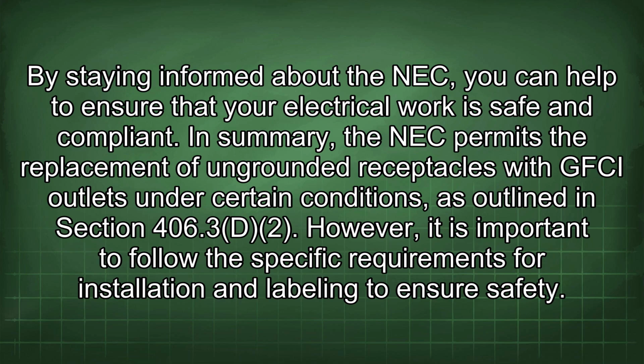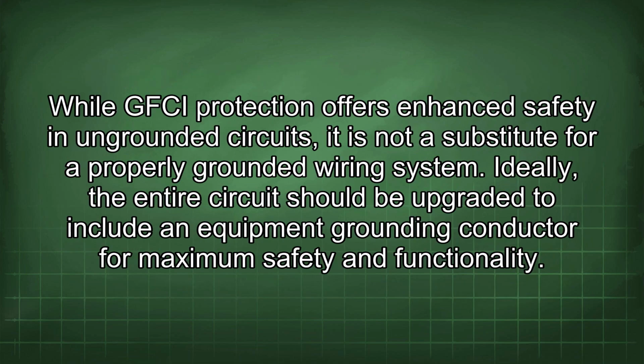In summary, the NEC permits the replacement of ungrounded receptacles with GFCI outlets under certain conditions, as outlined in Section 406.3(D)(2). However, it is important to follow the specific requirements for installation and labeling to ensure safety. While GFCI protection offers enhanced safety in ungrounded circuits, it is not a substitute for a properly grounded wiring system. Ideally, the entire circuit should be upgraded to include an equipment grounding conductor for maximum safety and functionality.